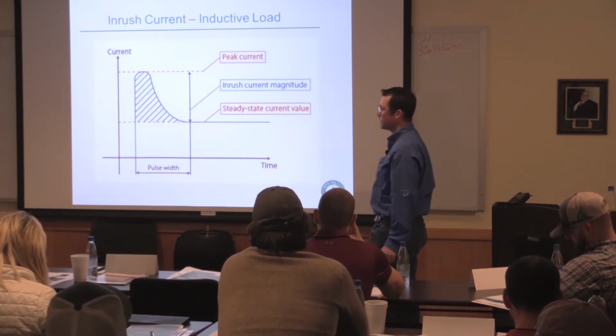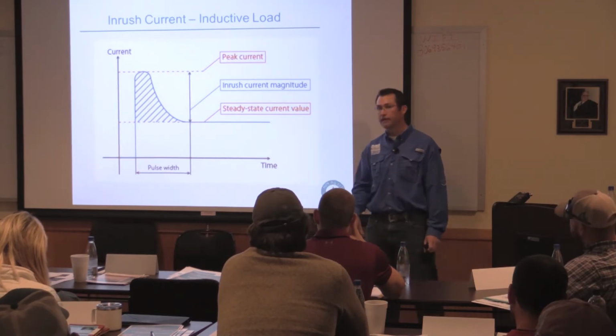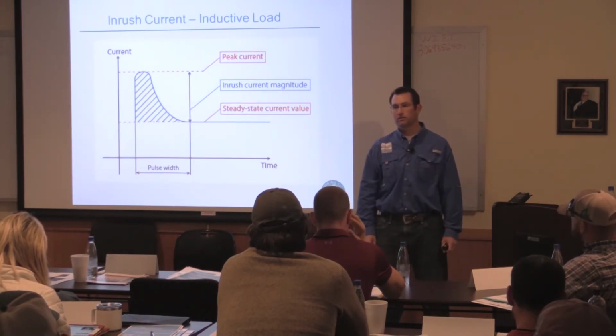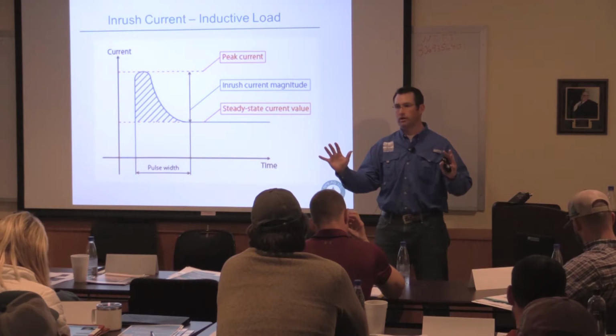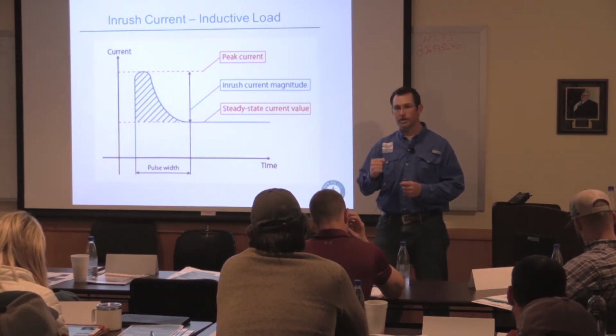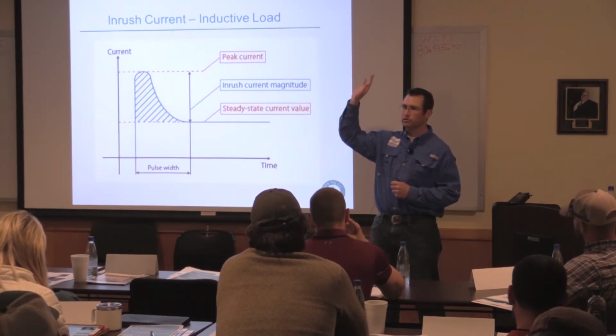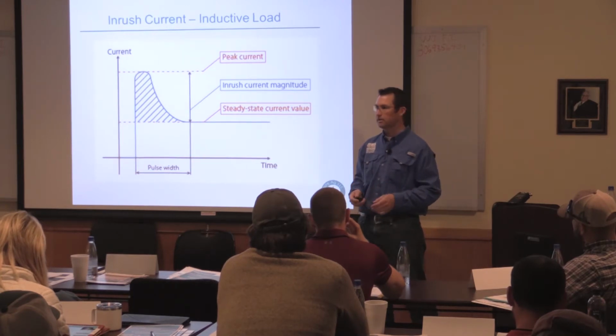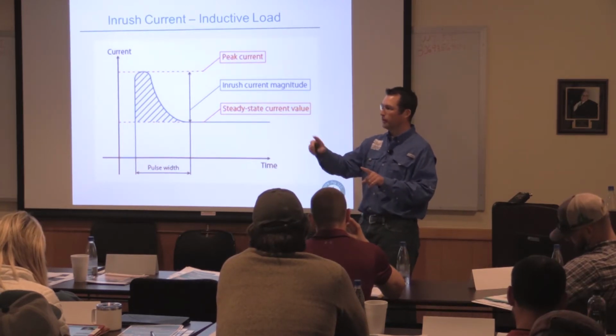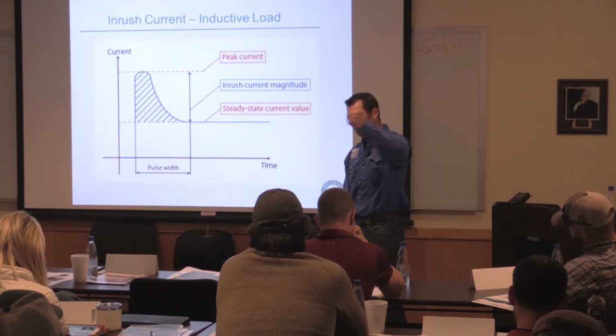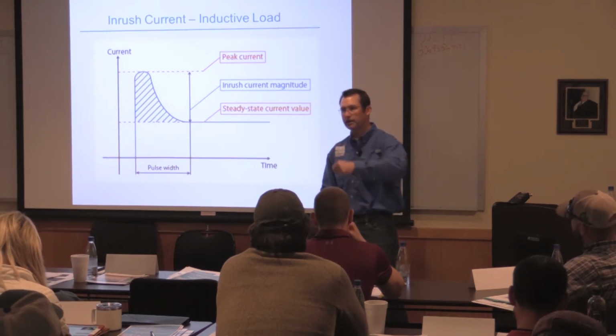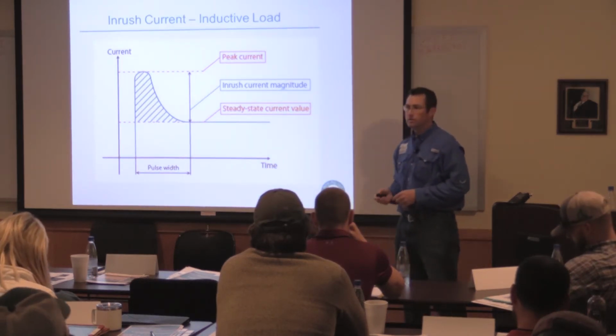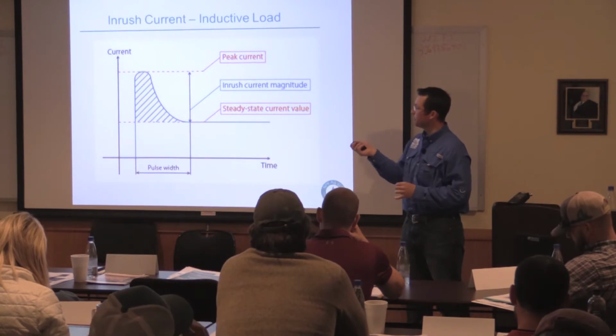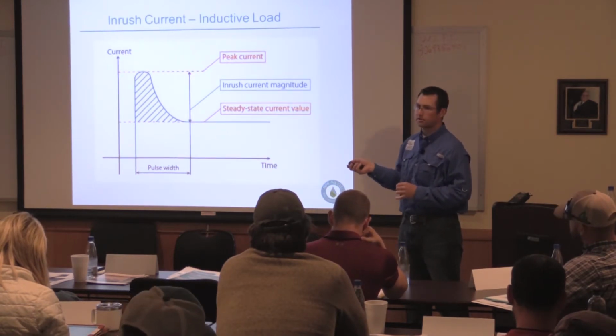Inrush current, the worst I've measured, is something in the range of 5 to 6x. That's a huge current. You've got a big old motor, when it hits hard, that current spikes huge, something like 1200 amps in some cases. I've watched it on an oscilloscope across the line, one of those old one-arm bandit starters, to see what it did, and I was just blown away. That really kills you even on your power bill if you're on the grid, because you're paying for that as your peak demand charge.